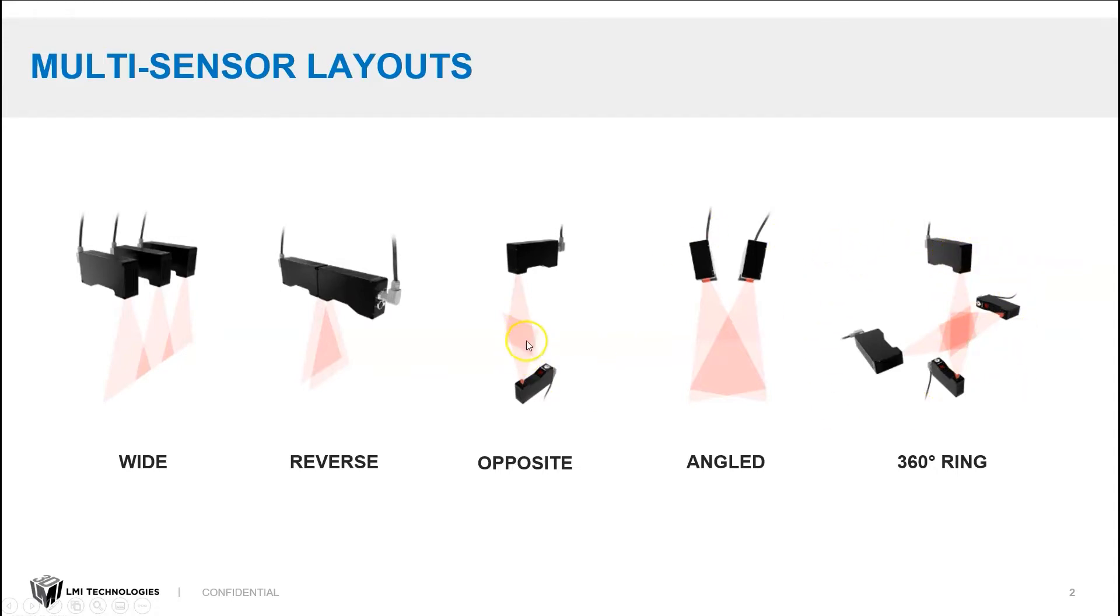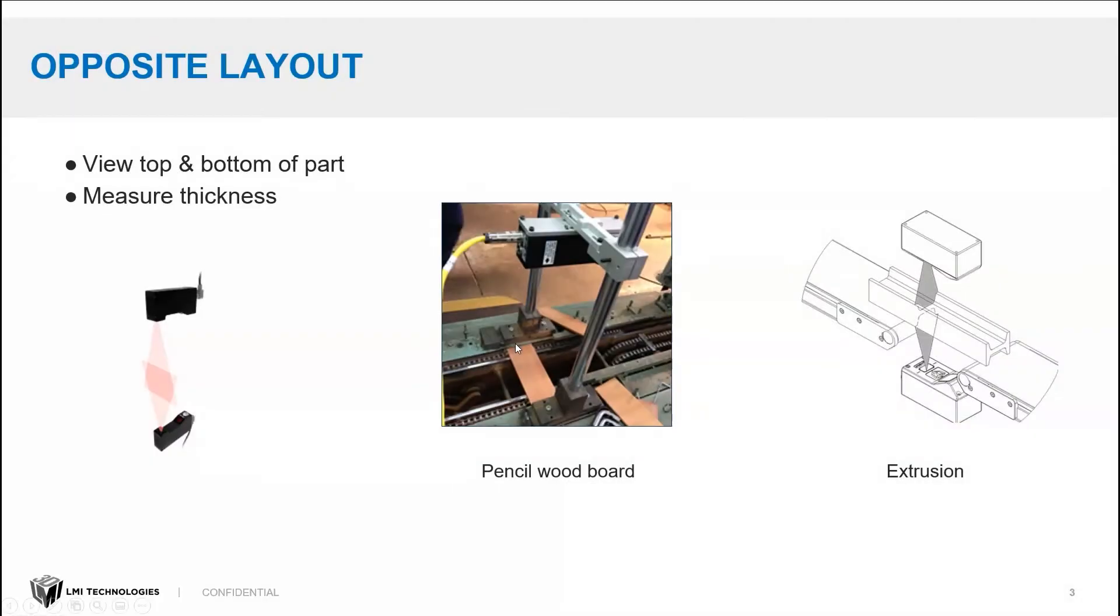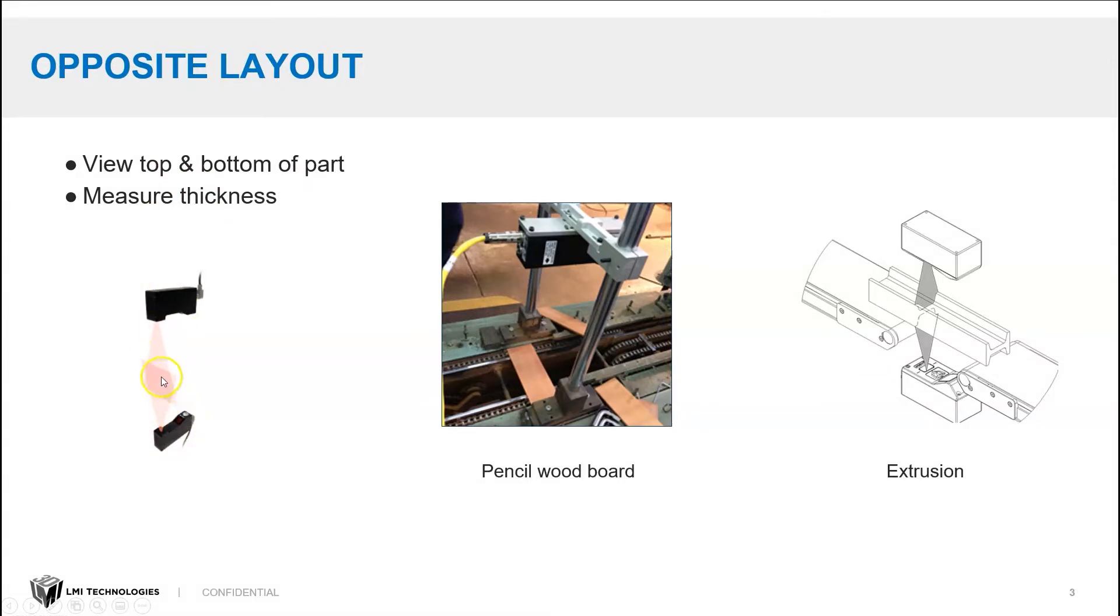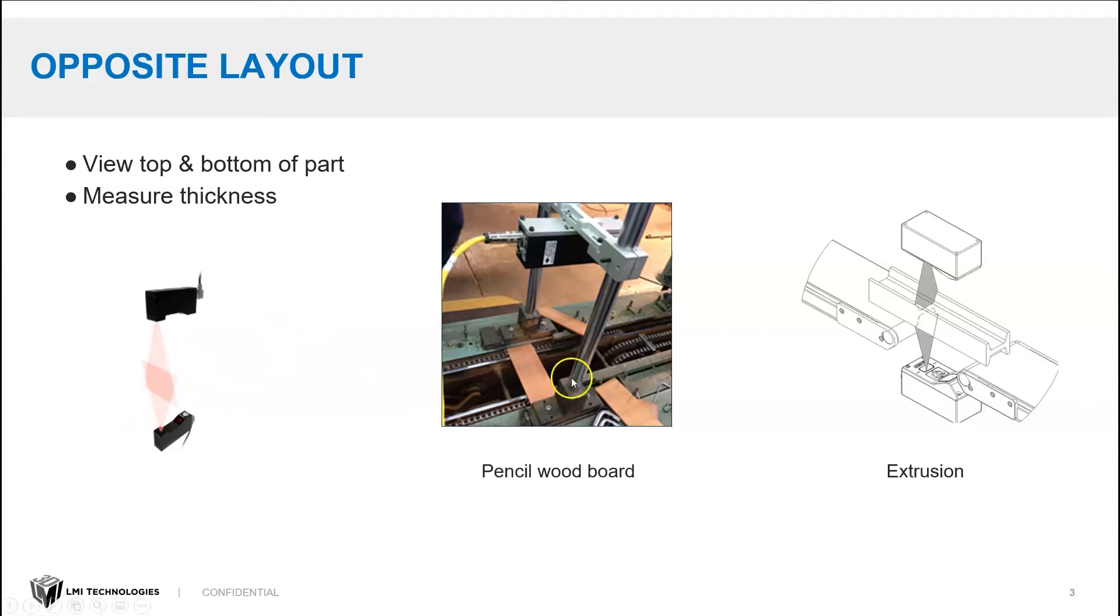But today, we're going to focus on the opposite layout. So in an opposite layout, you configure two laser line profilers facing each other, and the target is going to be in the region where they overlap. And this allows you to see the top and bottom of the part. It's particularly good for measuring thickness.